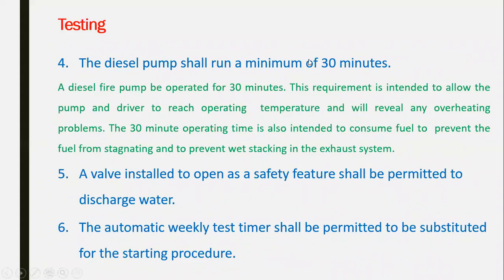What about the diesel pump? It has to run for 30 minutes. And the intent of this 30 minutes is to allow the pump and the drive to reach the operating temperature and will reveal any overheating problem. The 30-minute operation time is also intended to consume the fuel to prevent the fuel from stagnating and to prevent wet stacking in the exhaust system. So this one, getting all the system, the fuel and the oil system circulating, not stagnating.